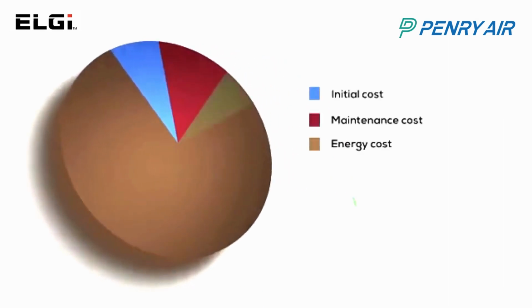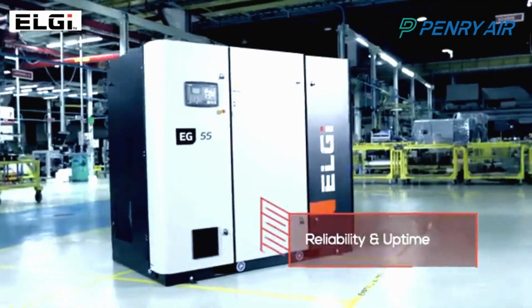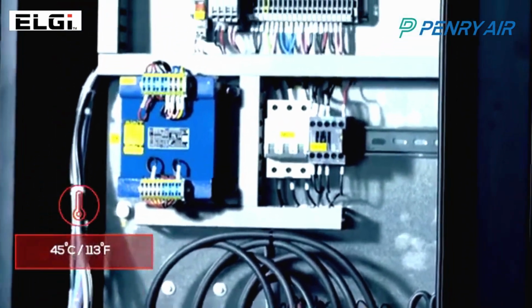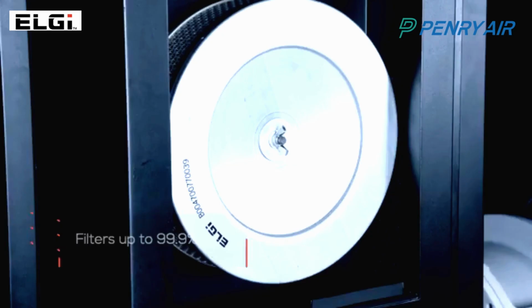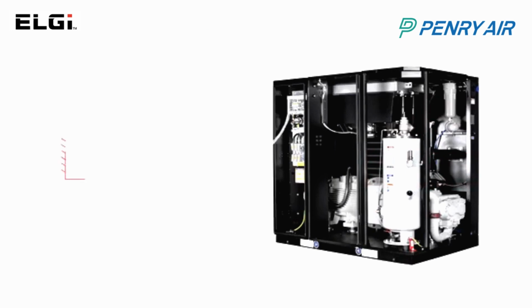The EG series compressors contribute up to 10% reduction in power consumption, translating into annual lifecycle cost savings for the customer. Reliability and uptime are ensured by leak-free, corrosion-free connections. All major components are designed for an ambient temperature of 45 degrees centigrade or 113 degrees Fahrenheit, ensuring operation in extremely hot environments. A multi-stage inlet air filtration system filters up to 99.9%. The oil separator efficiency has oil carryover of less than 1 ppm.